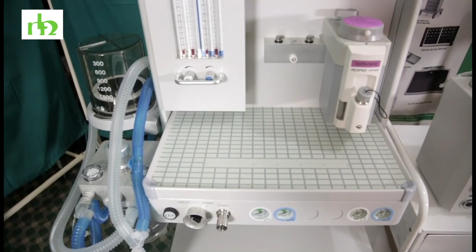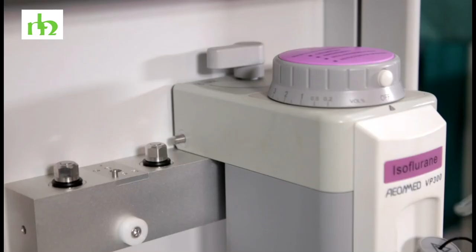It also has the capacity to support pipeline oxygen from the wall as well as cylinder. So this is the gauge measurement where you get to see the level of the oxygen remaining if it's connected to the wall and then if it's from a cylinder. So the cylinder can be hung behind the machine. And this machine comes with 2 vaporizers, halothane and isoflurane. It also has the capacity to support enflurane and sevoflurane vaporizers, depending on the customer's choice. We have 2 cabinets with this, 2 drawers cabinet, where the anesthetists can keep their products or accessories.